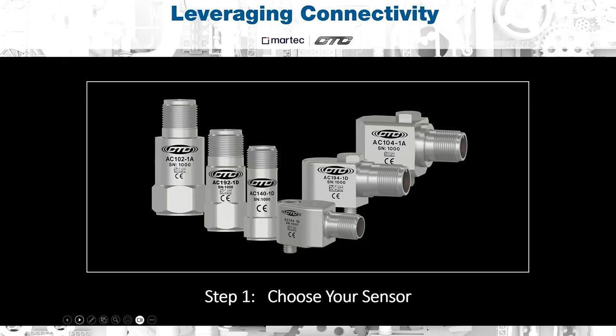Yes, thank you, James. That's a perfect example of an application where you can utilize the junction box, like you mentioned, the hazardous area where you're not able to enter that area and take a reading. So exactly, you can install that junction box outside of the area, but still be able to take the measurements from the reading. Again, I'll show some examples of the type of boxes that we have that you could potentially use for that type of application.